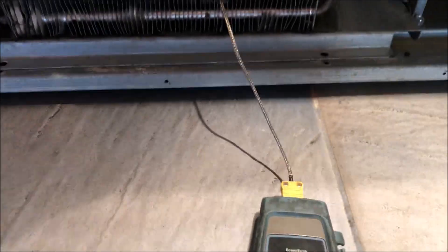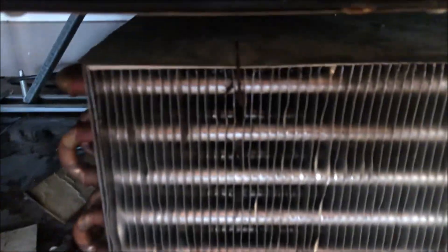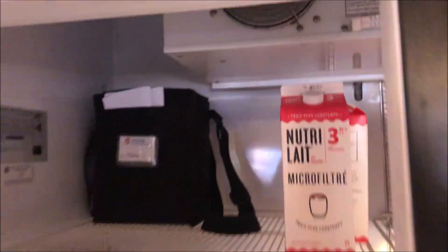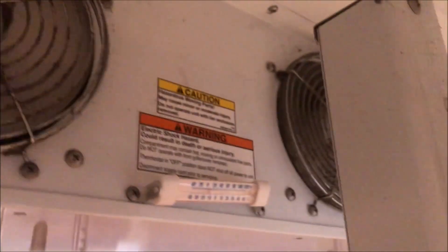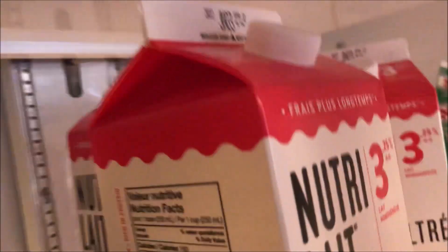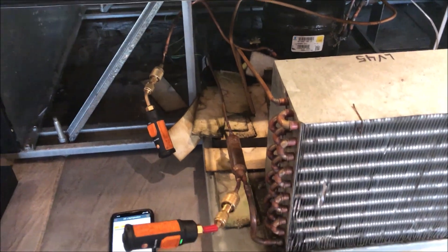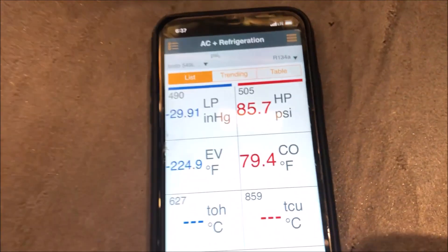Hey, how's it going everyone? Today I have a cooler that's not cooling. We're at 59 degrees. Let's do our general checks. Condenser's clean, condenser fan's running, compressor is running. Let's go check our evap coil really quickly. Fan one, fan two are running. And last but not least, let's make sure our coil is not icing up and we are good, clear of ice. So let's go ahead and gauge up and see what's going on.